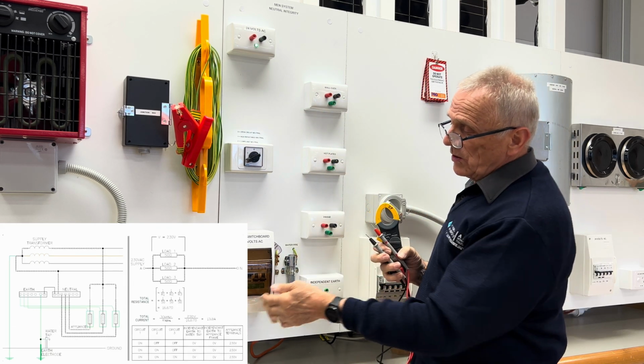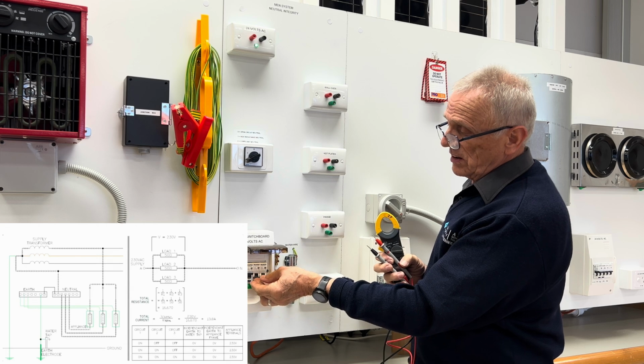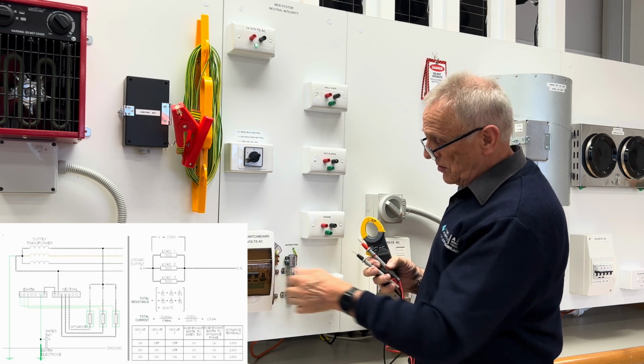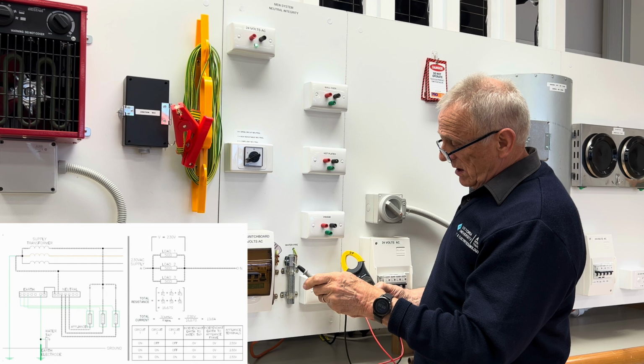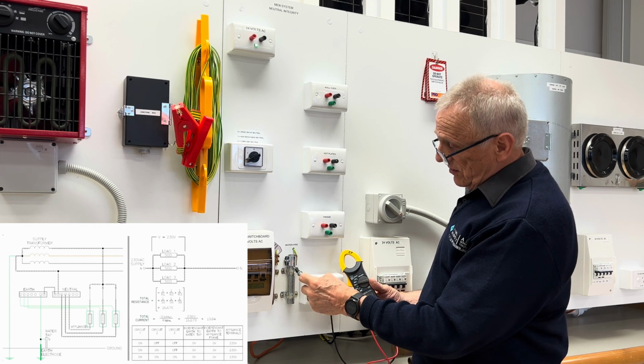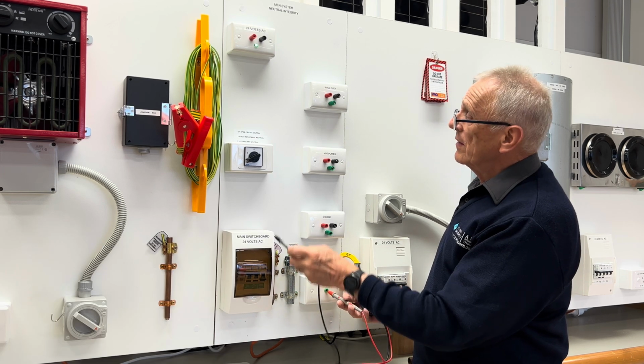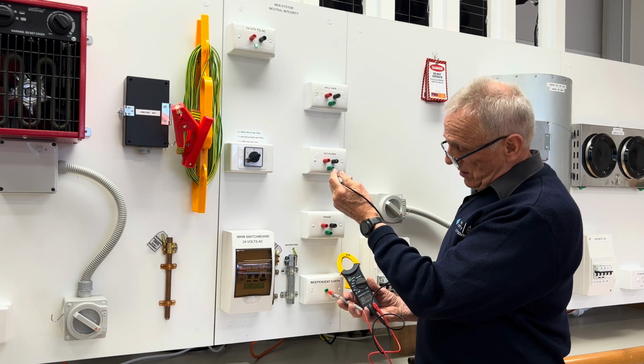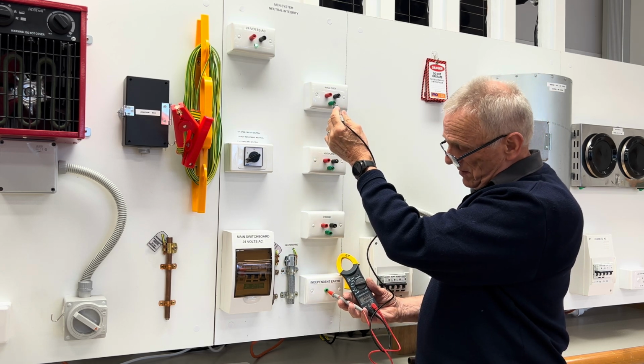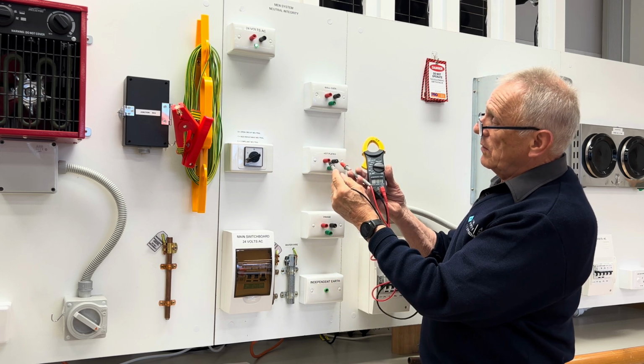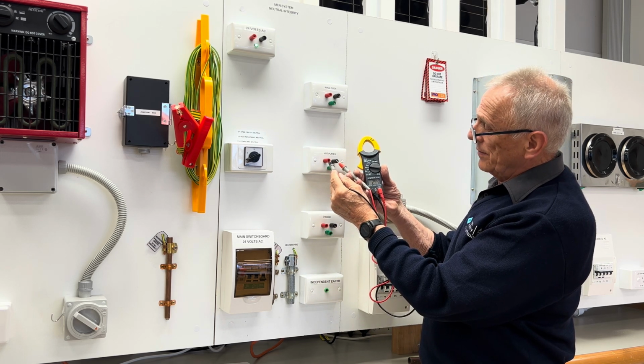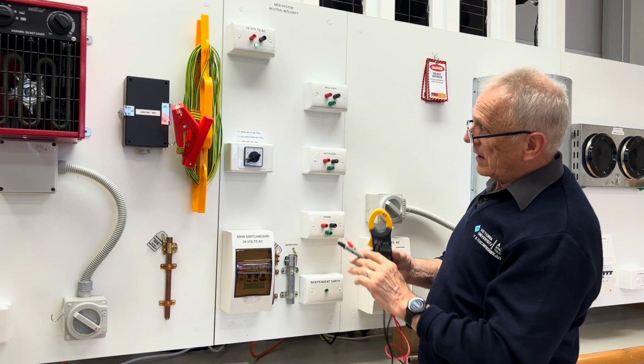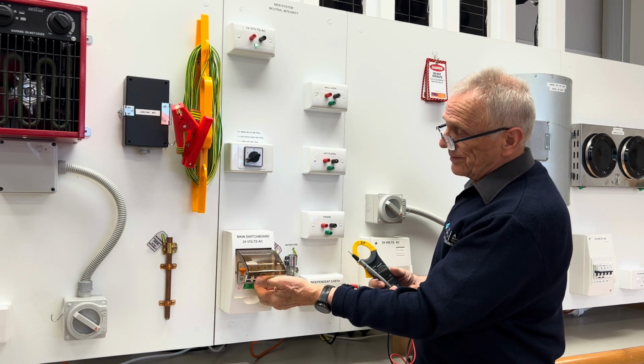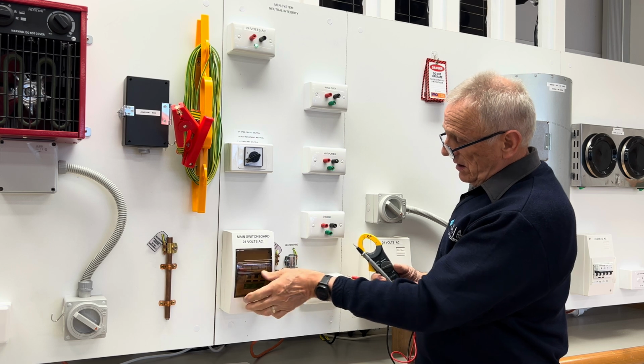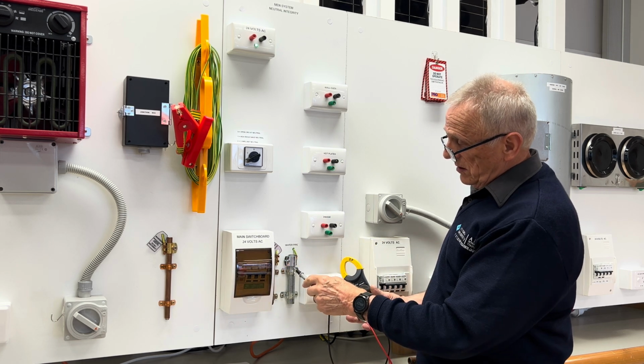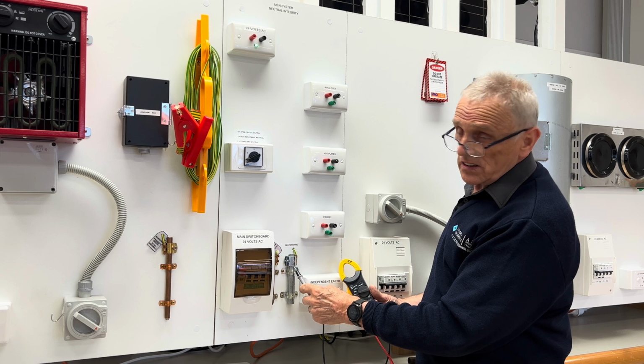Now, as we turn load on, there should be no fluctuation in voltages or on the earthing system. We can see now that there are 0 volts on the water pipe and also a hot plate. So both sets of equipment have 0 volts. We have 24 volts across the hot plate. Okay, and as we turn more load on, there should be no changes at all.